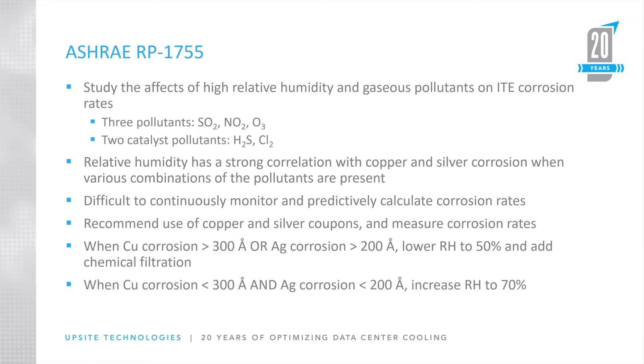That said, the key takeaway from the research project that ASHRAE TC9.9 has integrated into the fifth edition is that relative humidity has a very strong correlation with copper and silver corrosion when these different pollutants are present.